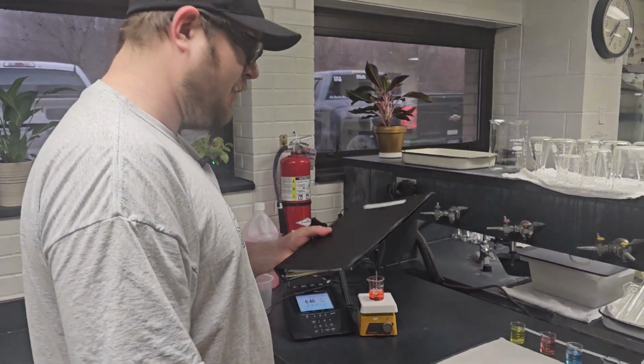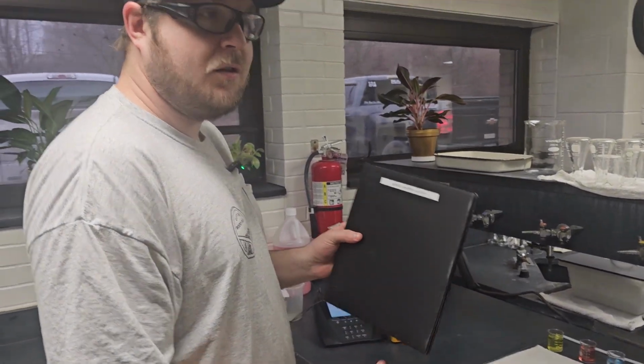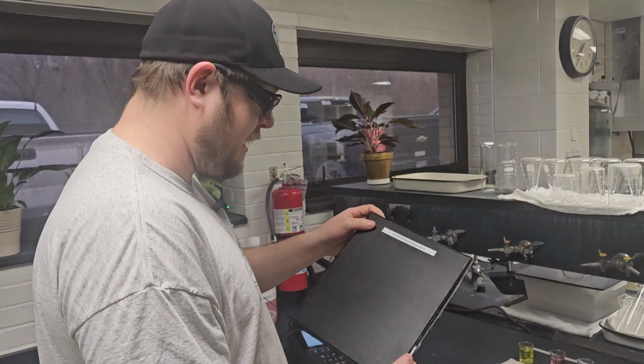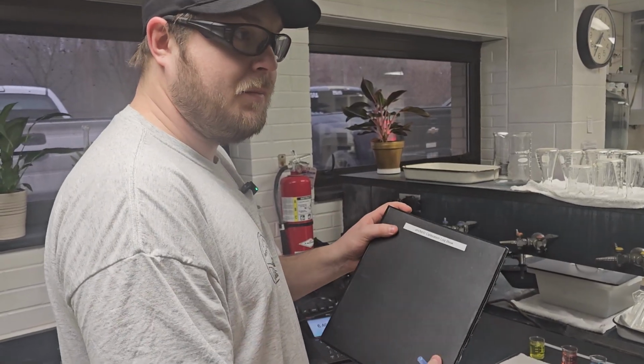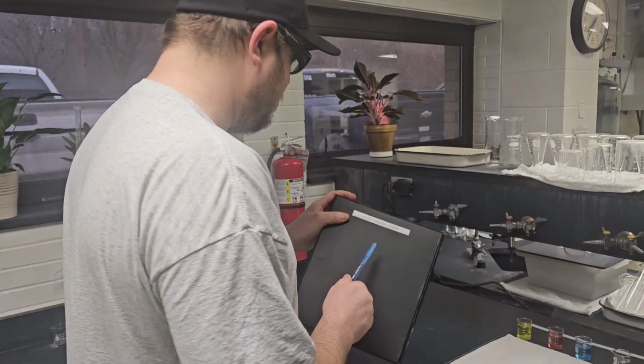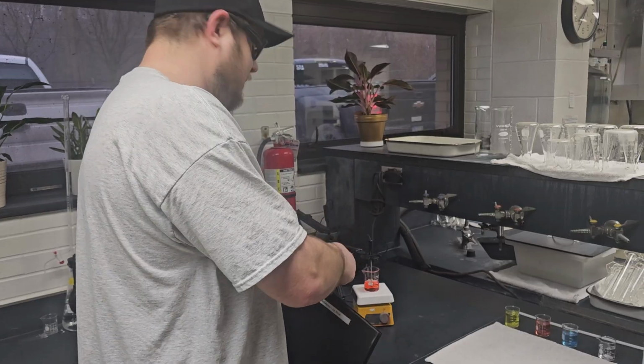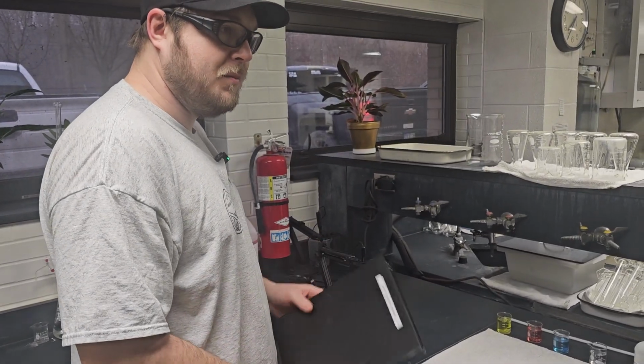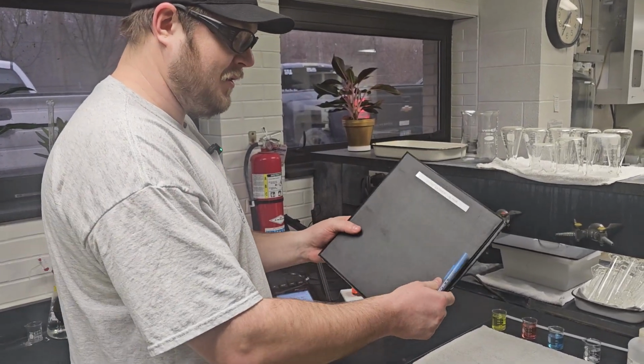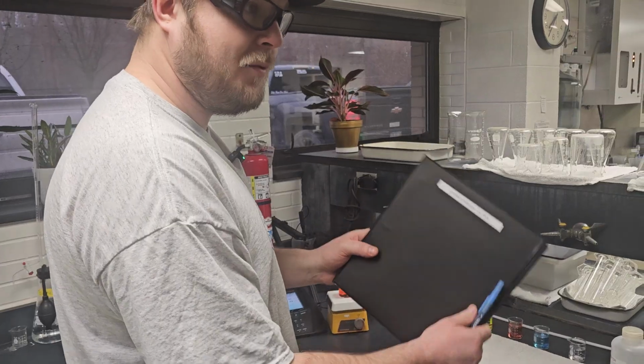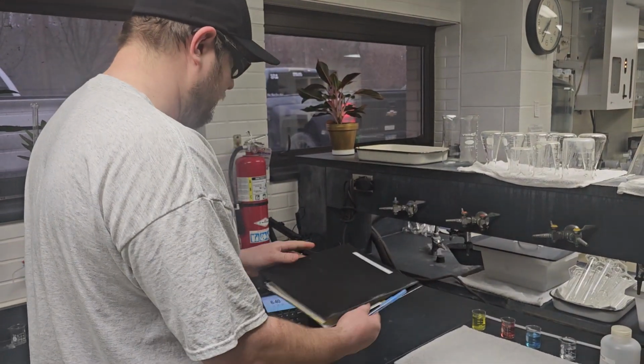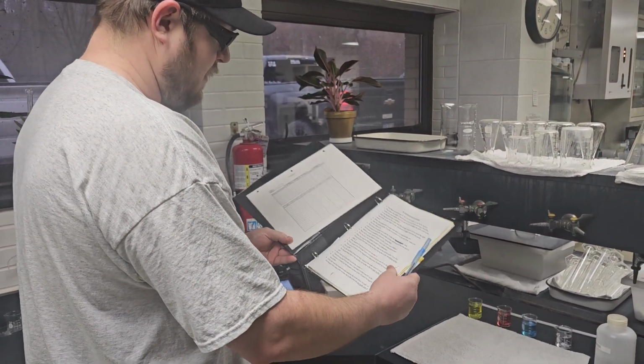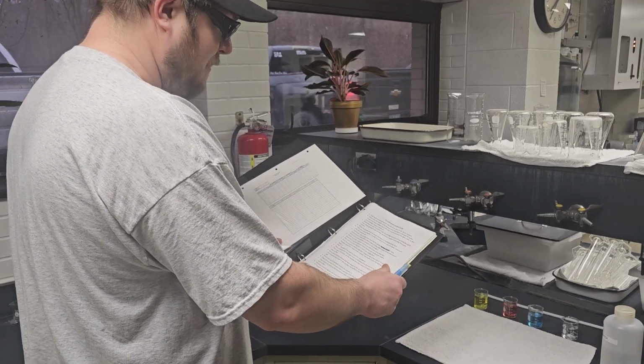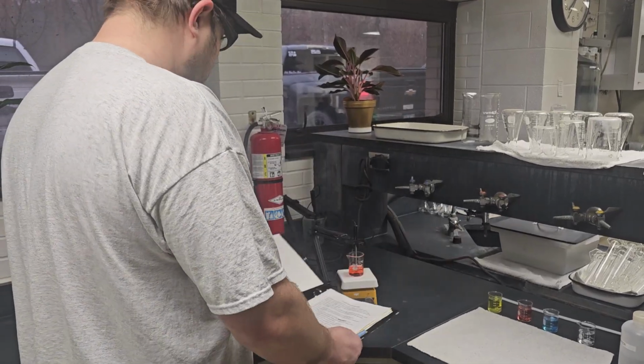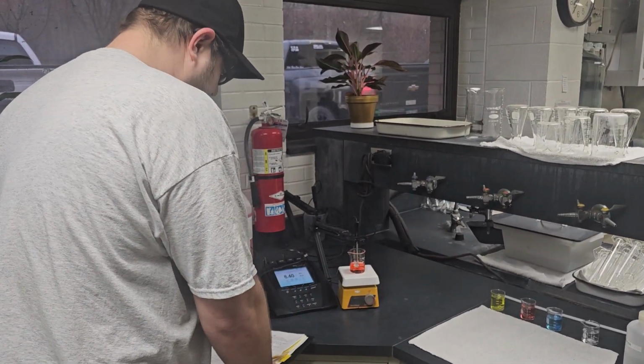When we have a low pH or are approaching our low limit of 6.5 pH, we need to confirm that the pH is correct by running a test on the lab pH probe. This is the lab calibration book. To start, we have to calibrate the machine. There's a guide inside the lab book on how to do this, and I will demonstrate now.